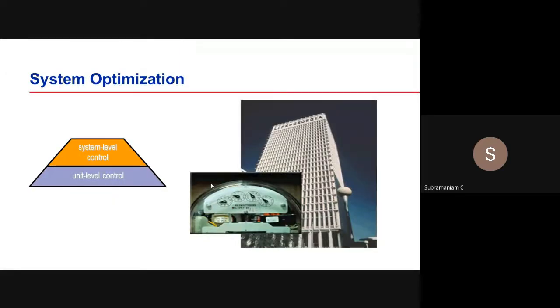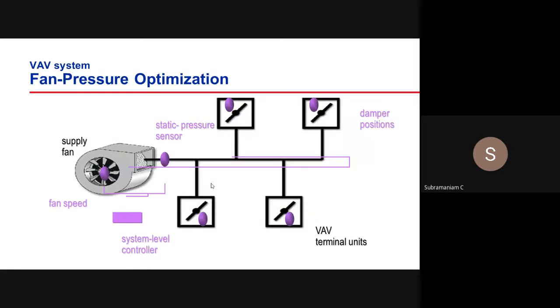Then that is in summary for you for unit level control. Now coming to system level control. System level control is what I told you about the chiller plant. For example, if you have 3 chillers, 4 chillers, 5 chillers in a plant, how many chillers have to run, how many pumps have to run, that is something a system level control has to decide. Or fan pressure optimization also, some of the vendors have got software where they can monitor the damper position and duct static pressure.